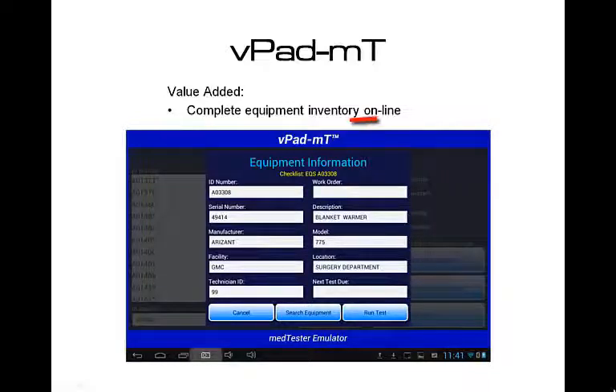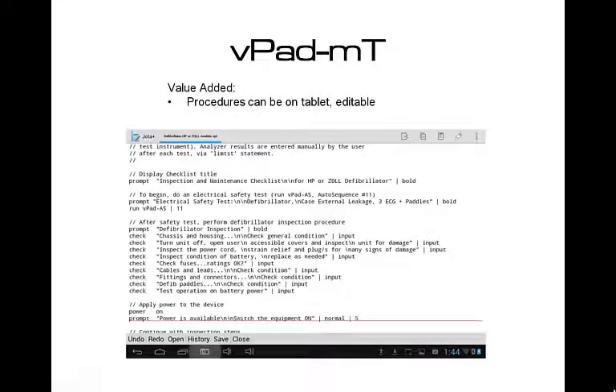For one, VPAD MT can support a basic set of data for the facility's complete equipment inventory online. If you enter a valid control or ID number, the basic equipment information form will be filled out for you. VPAD MT supports numbered autosequences above MedTester's maximum of 89. These autosequences are text files which reside on the tablet and can be called by a CMMS program simply by using an autosequence call. These autosequences use a simple scripting language called VPL and allow you to expand your check procedures with instructions that were not possible before.